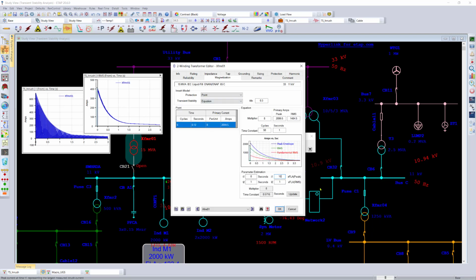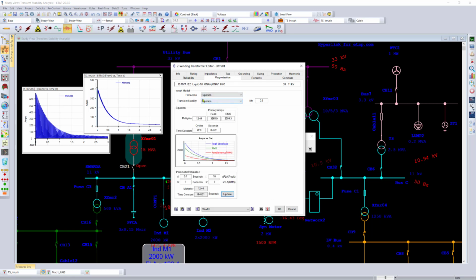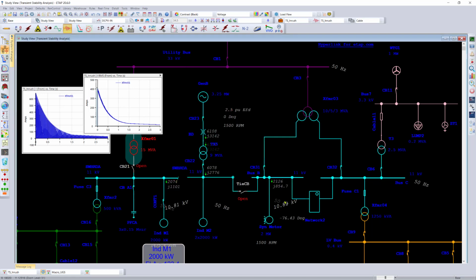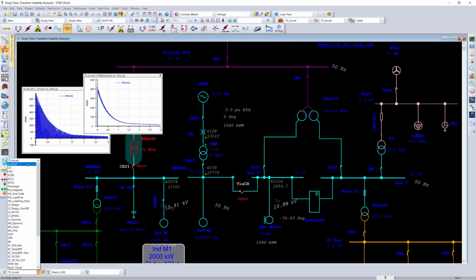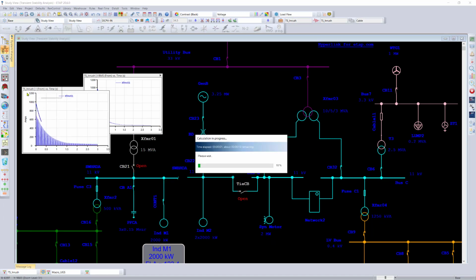If we assume that the inrush peak is 10 and the time at which the peak occurs is 0.1 seconds, we can see that our inrush multiplier is 12 times, and this is our time constant. We can then go ahead and update our inrush value, and then this equation-based calculation can be used by transient stability as well as ETAP Star for protection and coordination. We can simply go ahead and run our inrush simulation again and see the difference in results based on the new parameter estimation from the program.